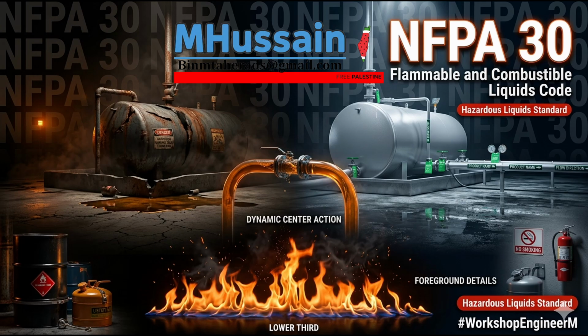Exactly. Now, the code notes many drums can technically hold up to 44 psi before failing. But the failure mode in a fire is not a slow, polite leak. No, it is a dynamic, catastrophic rupture. The hoop stress overcomes the tensile strength of the steel, usually the seam where the lid is crimped to the shell. And when that seam yields, the drum rapidly depressurizes. All that superheated liquid inside instantly flash boils, expanding its volume exponentially in a fraction of a second. This is what the industry calls a BLEVE, a boiling liquid expanding vapor explosion.